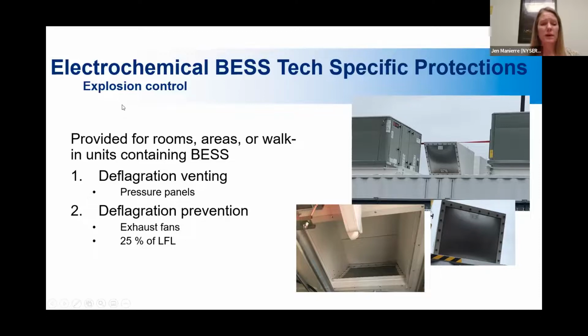So 2 options for explosion control. And again, this does apply to lithium ion. You can either have that deflagration venting to direct explosions where you want them to go, or deflagration prevention, which again is why you might see exhaust even in lithium ion systems, because if something's going wrong, they might start exhausting, or off gassing rather. So you want exhaust fans that will keep that off gassing to 25% of the lower flammability limit to prevent explosions from happening in the first place.